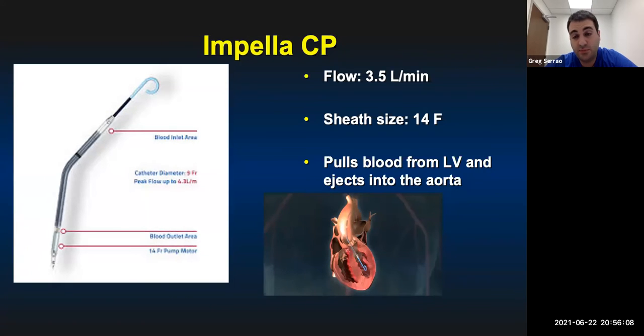This provides up to 3.5 liters per minute of flow, which is a lot of flow for a patient in cardiogenic shock. The downside is that the sheath size is a lot bigger. So compared to the 7 French balloon pump, this is 14 French, so double the size. And for that reason, the vascular risk is much, much higher, more than double the vascular risk. But the concept is an important one of pulling blood from the left ventricle and ejecting it into the aorta.